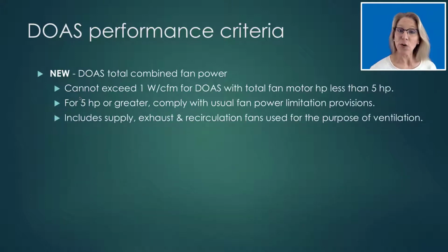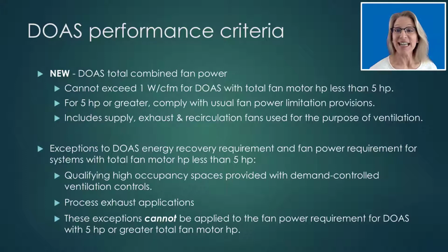And note that that 5 horsepower threshold needs to include the fan power for the supply fan, the exhaust fan, and any recirculation fans like a ceiling fan that is used for the purpose of ventilation. The exceptions that allow a DOAS to not have energy recovery haven't changed. However, note that the fan efficiency requirement exception only applies to DOAS with total fan motor horsepower less than 5 horsepower. For those larger systems, you have to comply with the usual fan power limitation provision, as usual.